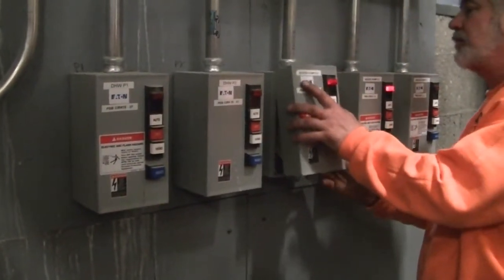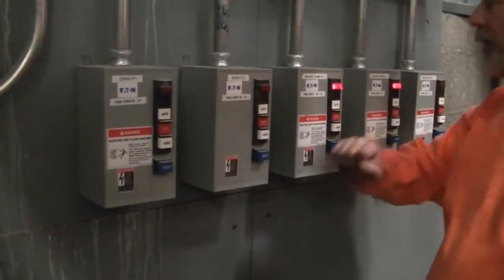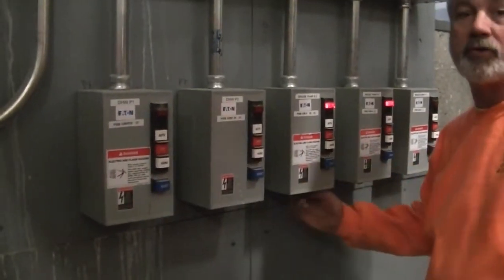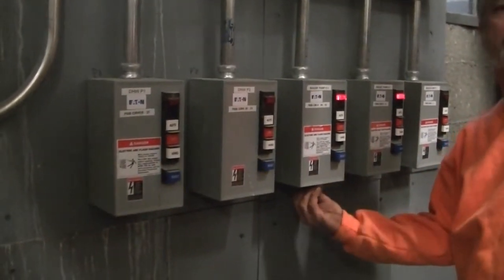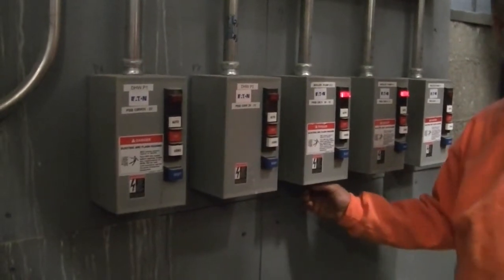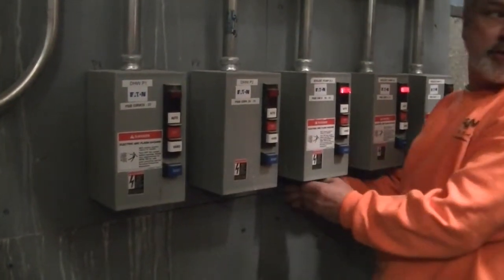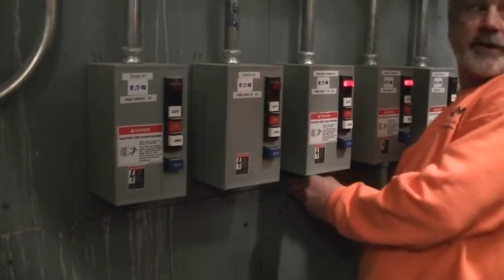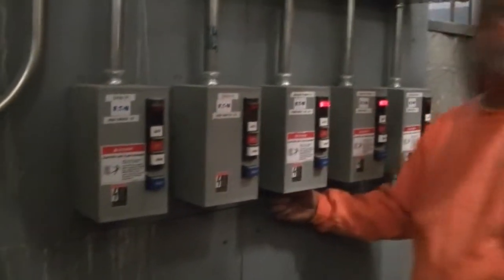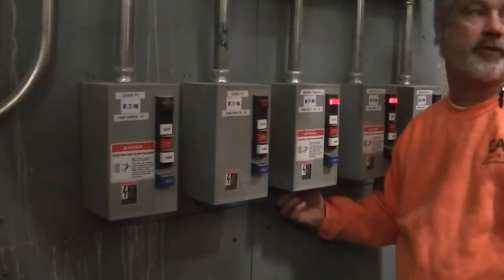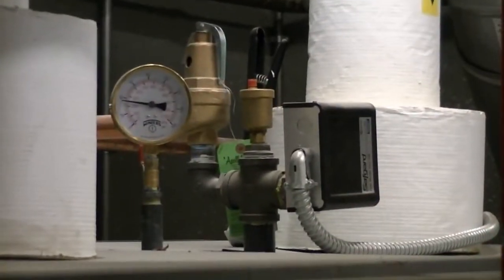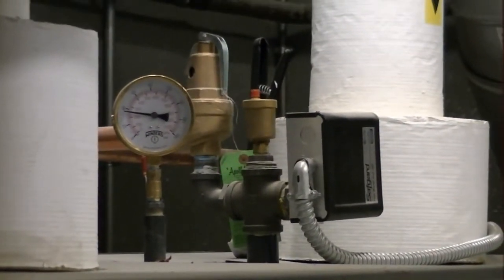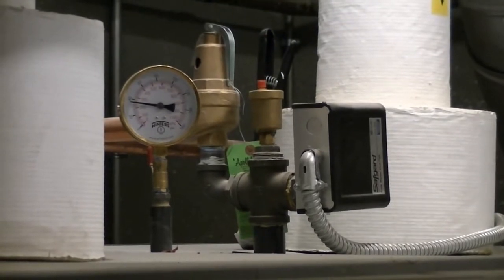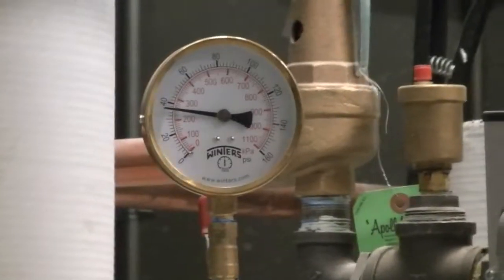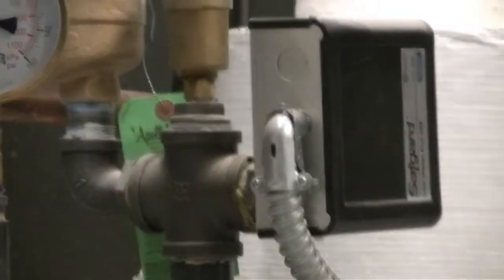I don't know if Kevin went over anything else on the boilers. The boilers also have low water cutoff controls on them. Did he mention that? Okay. On the top of each one of the boilers, you'll see a cross T. On that T, there is an automatic vent that vents any residual air that gets in the boiler. That's a low water cutoff. On the side, same low water cutoff you'd see on any residential or like commercial boiler. Okay. It's got a test and reset button on it.